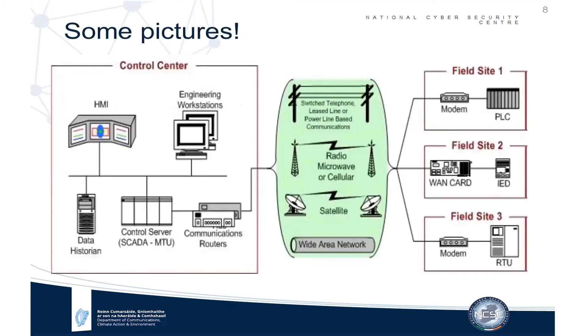Here is a diagram of a SCADA system. On the left-hand side is the control center: the HMI, engineering workstations, data historian, control server, SCADA master terminal unit, and communications routers. On the right-hand side are different field sites — one, two, three — which SCADA controls out in the field across different parts of the country. Field sites may contain PLCs, intelligent electronic devices, or remote terminal units, with a communications link between the control center and field sites.